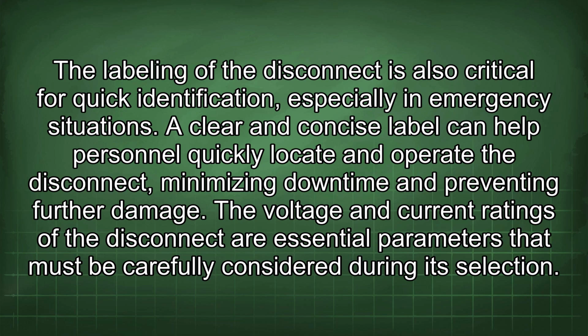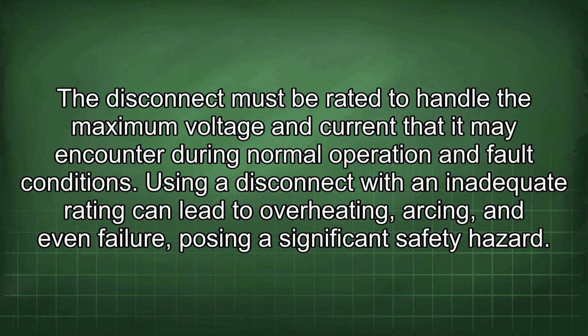A clear and concise label can help personnel quickly locate and operate the disconnect, minimizing downtime and preventing further damage. The voltage and current ratings of the disconnect are essential parameters that must be carefully considered during its selection. The disconnect must be rated to handle the maximum voltage and current that it may encounter during normal operation and fault conditions. Using a disconnect with an inadequate rating can lead to overheating, arcing, and even failure, posing a significant safety hazard.